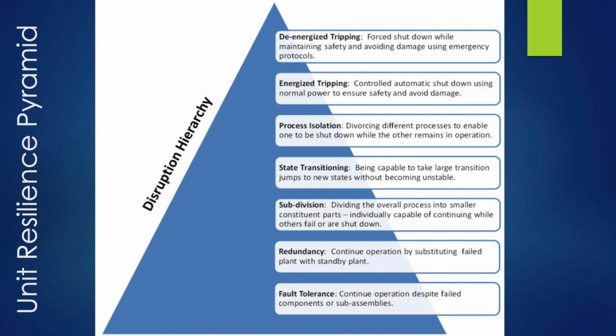Now and then one of these disturbances will breach the barrier you've got, your resilience barrier will be breached. If it breaches, you try for it not to activate a common mode type failure, so it should just shut itself down and not start a cascade. But now and then a cascade event would be initiated, and dominoes start to fall. Then you've got a cascade containment barrier, designed and maintained to stop such a cascade from escalating too far. However, if that breaches, you have a blackout.